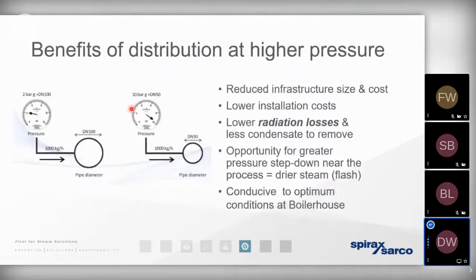And in the vast majority of building service applications, we're typically talking about a high pressure of 10, maybe even 12 bar gauge. The reason being is that the rate at which we can compress that steam volume is going to start to plateau off, and we're not going to see too many cost savings by being able to reduce the infrastructure much further. But the little graphic really helps to emphasize the fact that if we can increase the working pressure of the steam boiler, then we can distribute the steam at a high pressure in a very small pipe diameter.